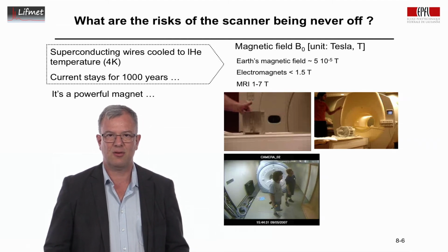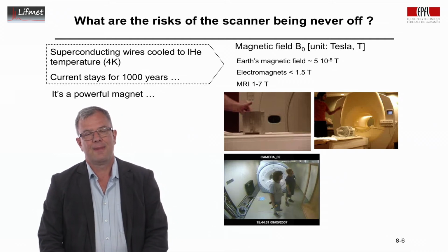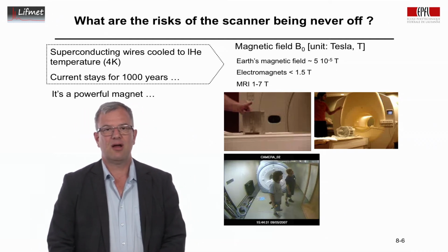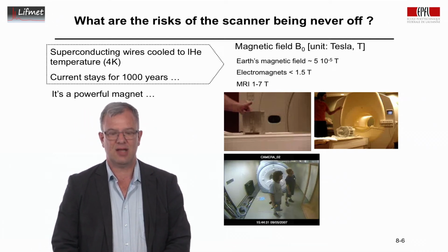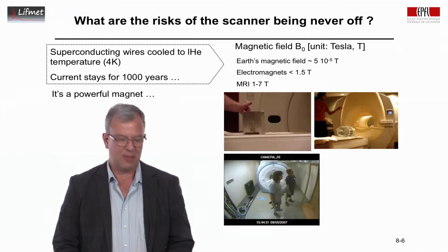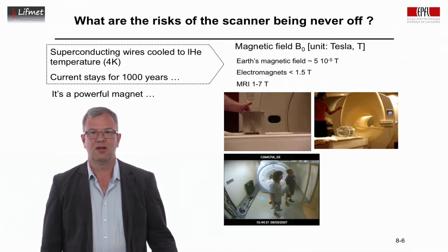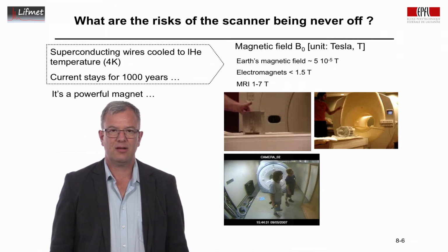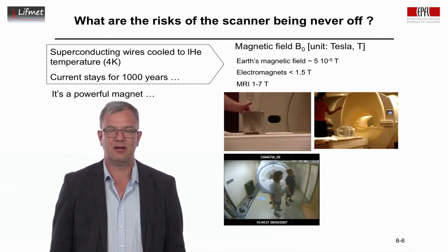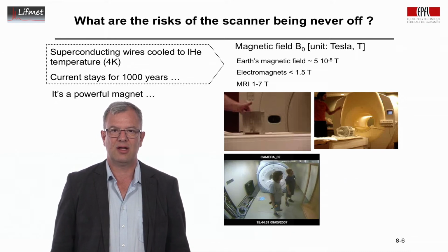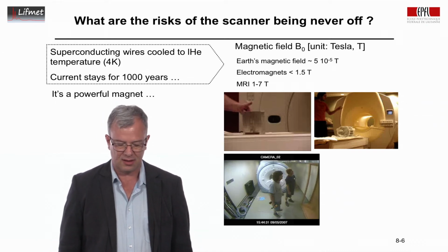Batteries are typically ferromagnetic. As he was moving around in the room, he wasn't paying attention to the magnet in the back of the room, and as he got too close to the magnet, the magnetic field attracted the drill. He could no longer hold on to it, and it flew inside the magnet.